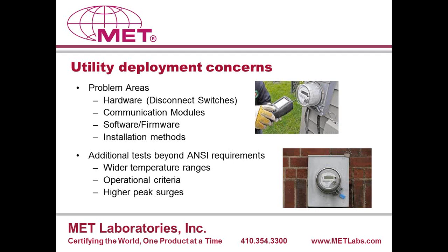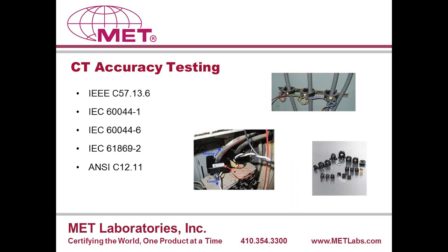Utility problems with equipment in the field once it's deployed. Again, MET can really be an advantage for you to help develop a test program, either a certification program, an ongoing type of testing program, what have you, whatever the case may be, whatever you're looking for to help you meet the needs of either your buyer or to identify issues that you're seeing in the field. Our CT accuracy testing, there are the standards that we are able to test to, the IEEE C57.13, the IEC standards, the 60044-1 or -6, the IEC 61869-2, which essentially supersedes the others, but we still see requests for the 60044-1. And there's also an ANSI standard that has to do with CT testing as well. At the moment, we do not have VT testing, but that is something that's probably coming down the pipe before too much longer.